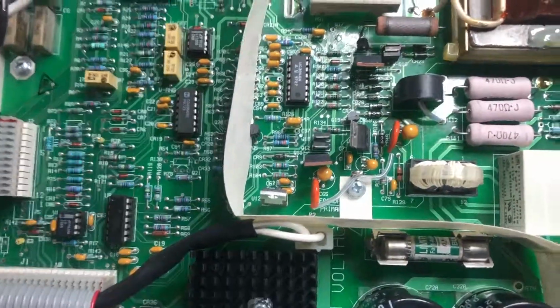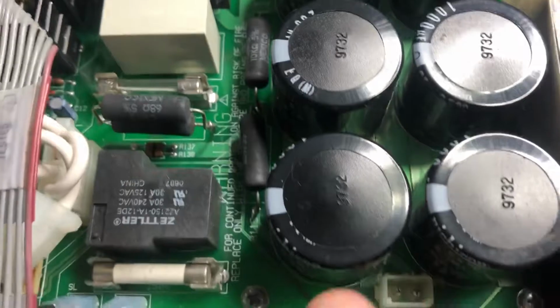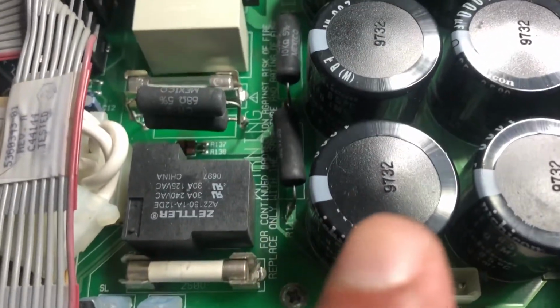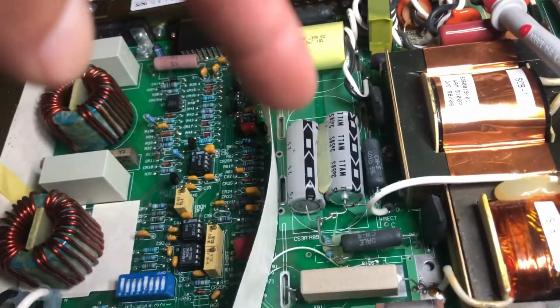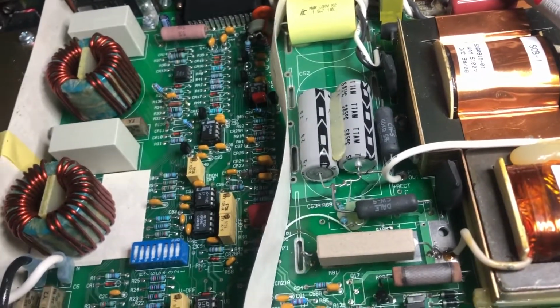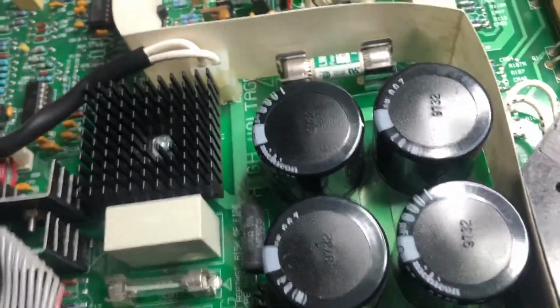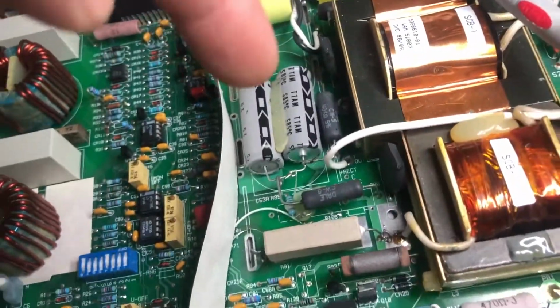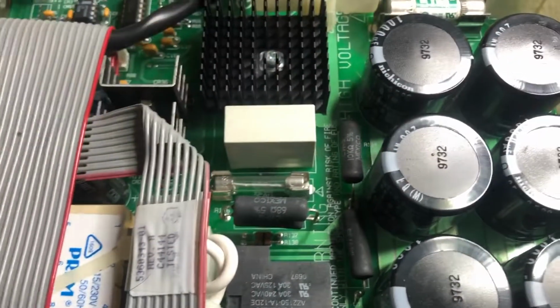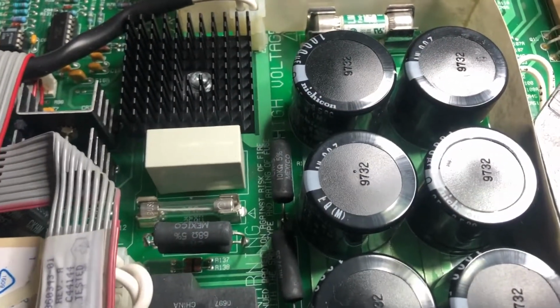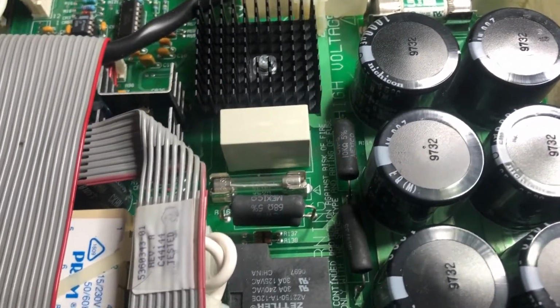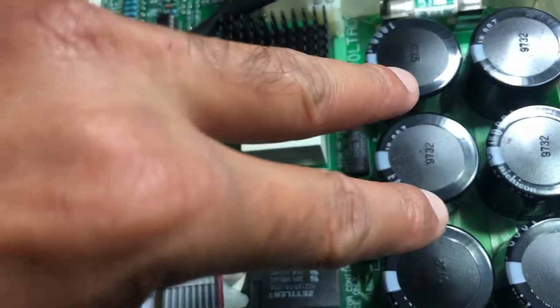That's the drive output. Another point about the capacitors - I haven't really checked the ESR of these capacitors, or these guys around here, to make sure they're okay. I assume they are okay, but I'm going to check the ripple at a later point to see if it's really good. If these capacitors are dried up, you may have to replace them to get a better, lower ripple in the output. So just be careful of these things - different models come with different sets of capacitors, but hitting the same value.